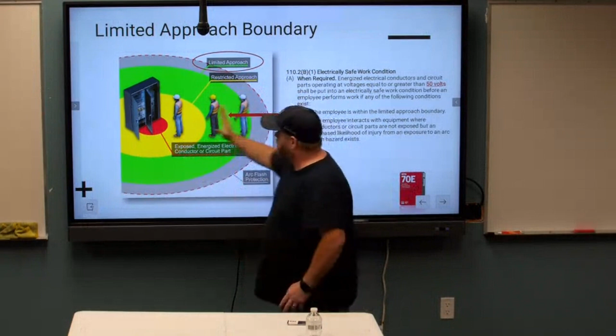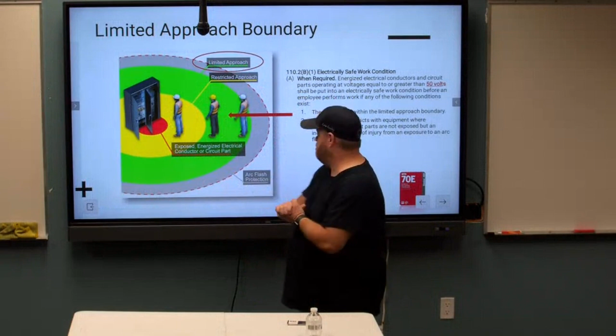Now these two shock boundaries, or approach boundaries, are completely independent and separate from your arc flash boundary. Your arc flash boundary, this red dotted line, sometimes it is your biggest boundary and sometimes it's not. Sometimes it's in here somewhere. It all depends on the study that was done by that engineer. Does that make sense? Got a question from Caden.